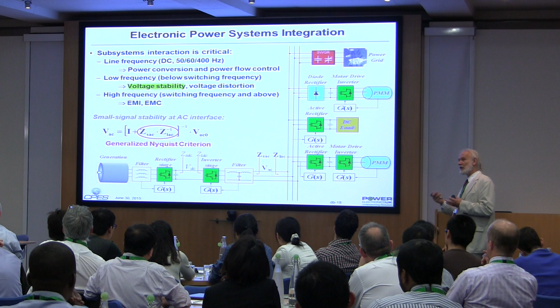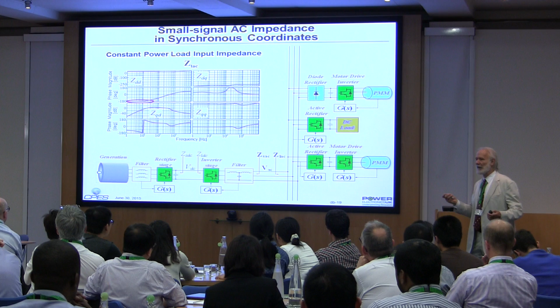We were really asked to do this, and it turns out - this is mathematical theory, probably 20 years old - that if you look at the impedances in the synchronous D-Q coordinates, aligning D with the power flow and Q orthogonal to that, so D corresponds to active power flow and Q to reactive, then loads that are all power converters appear as constant power loads. At low frequencies they have some value with negative real impedance. That's a cause, or possible cause, of instability.